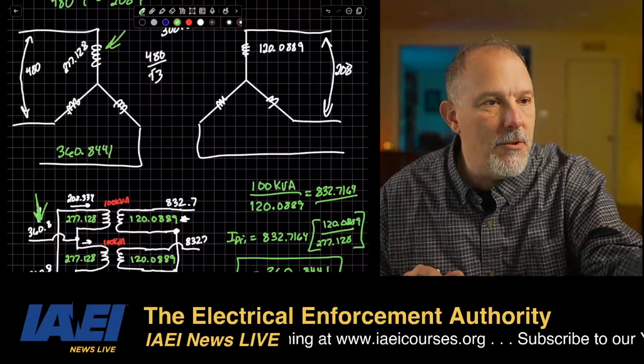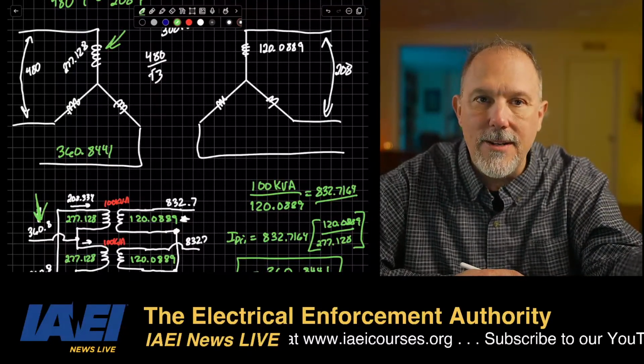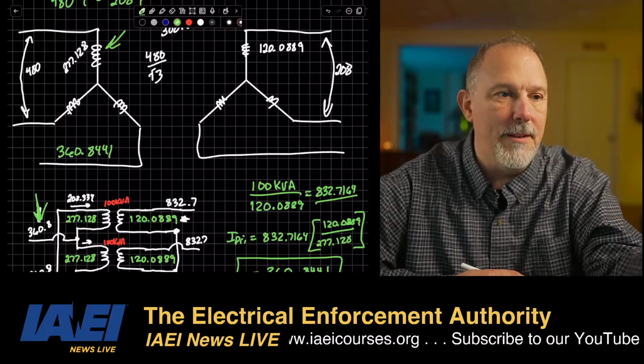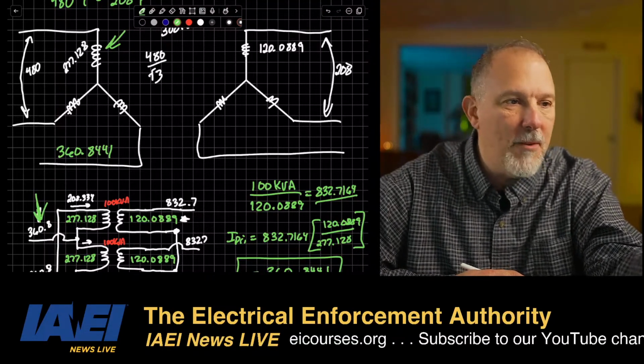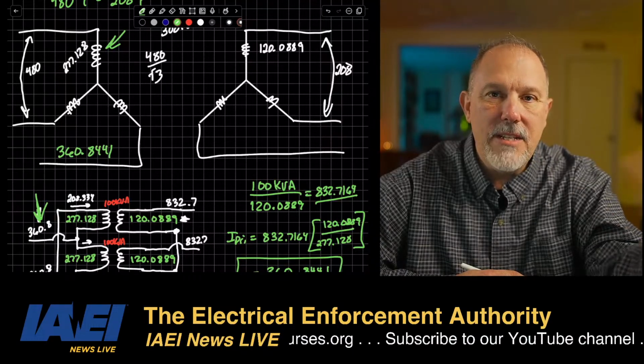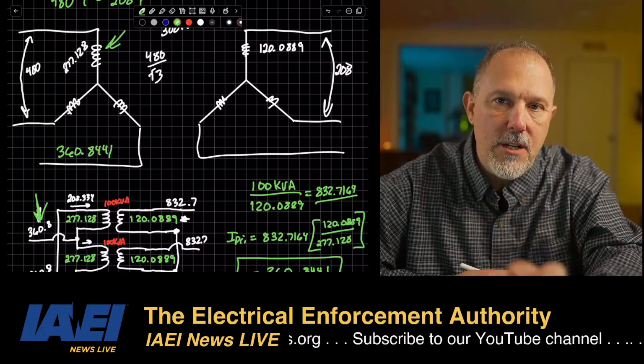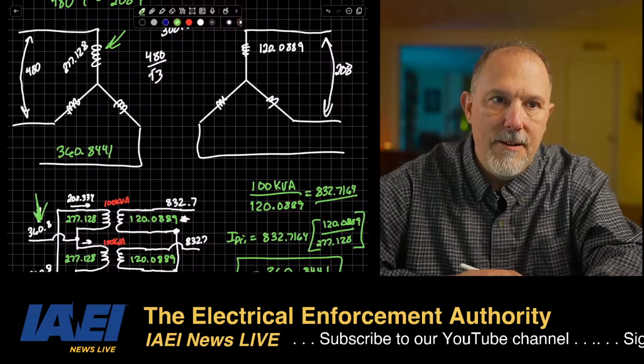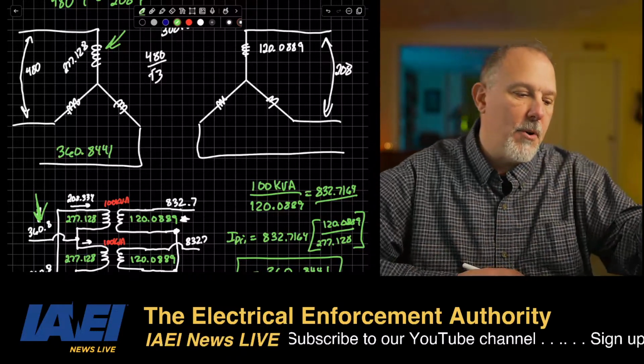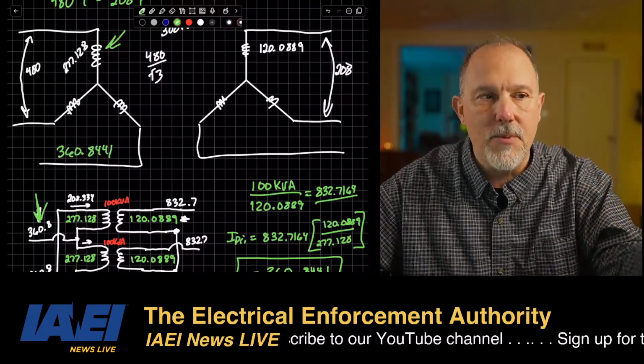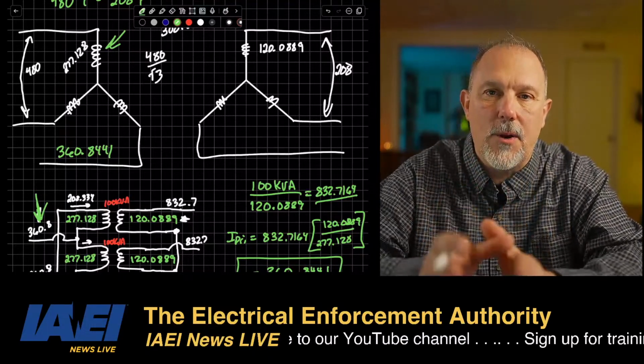It's a screwed up turns ratio, right, Dawn? 3.997 to 1. 2.31 to 1. These things are screwed. The ratio, if you do the math, N1 over N2, primary voltage over secondary voltage, the numbers don't look right. It's because of the square root of 3.